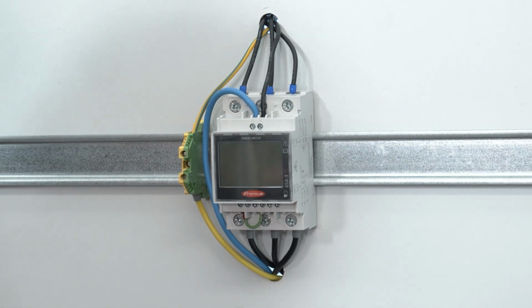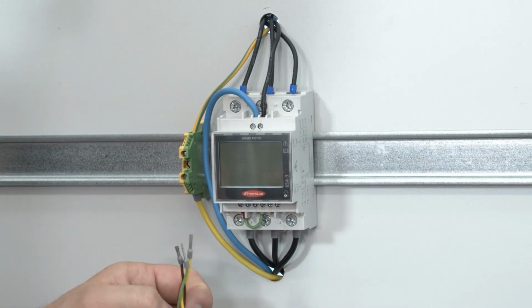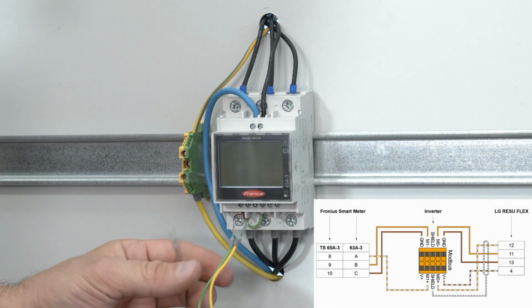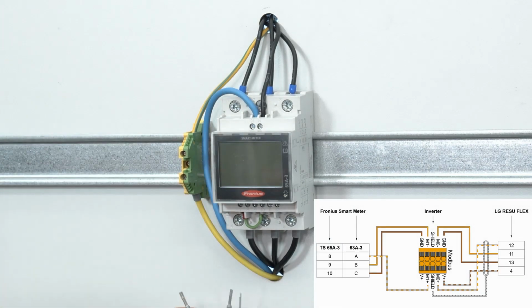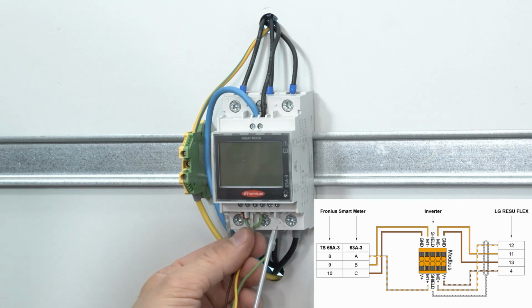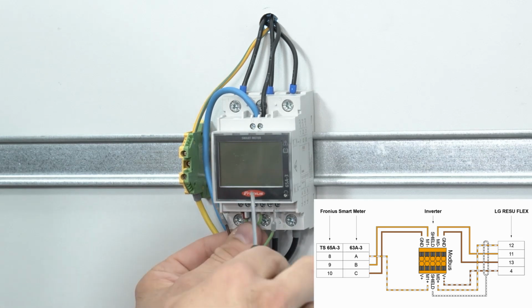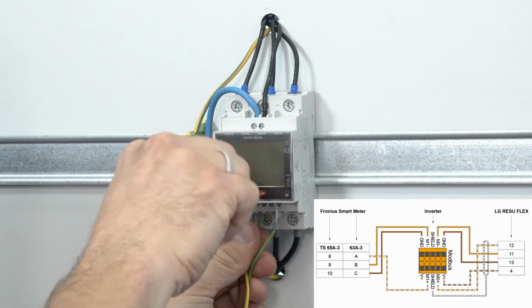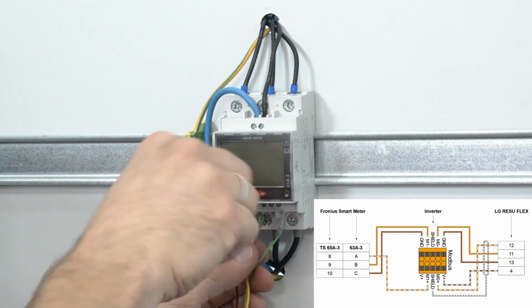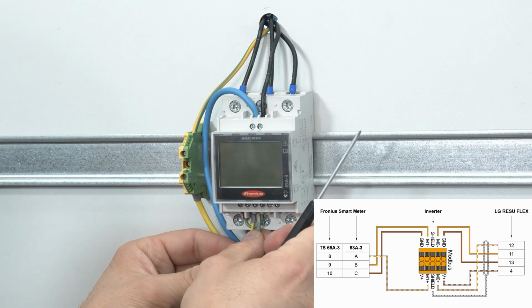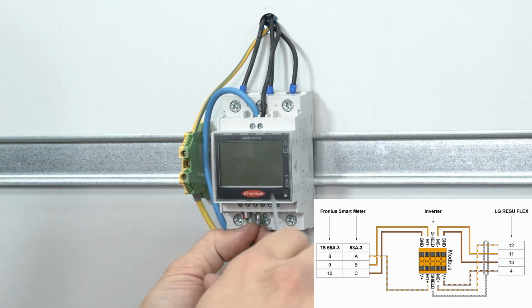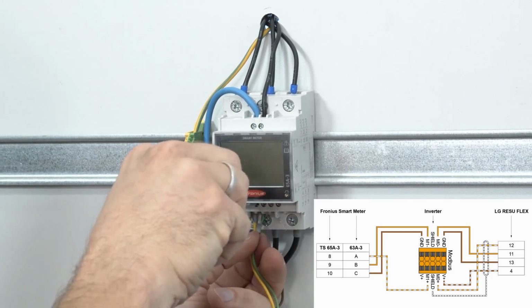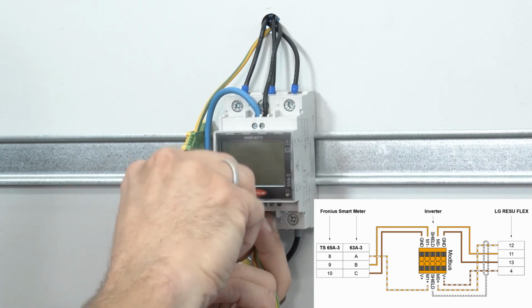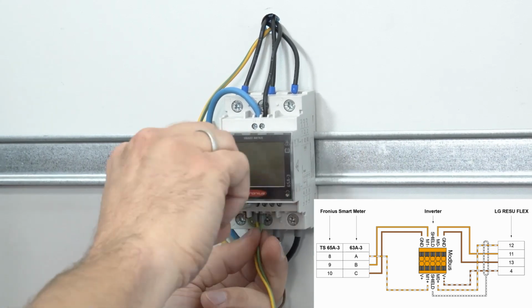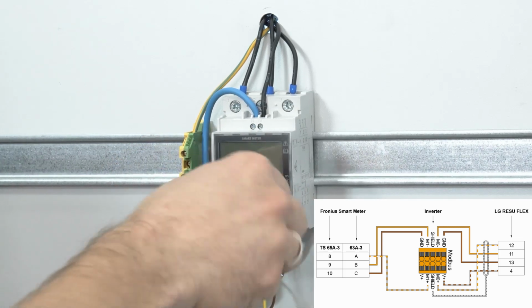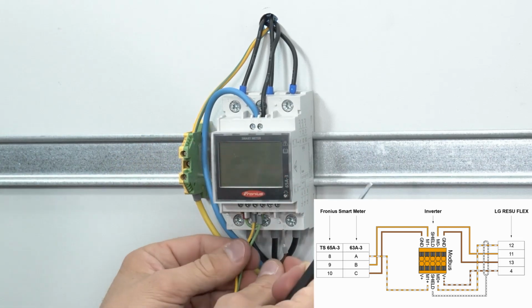contact number 9. And then for the Modbus communication we are again using our data plus, data minus and ground cable, and therefore we are starting with contactor number 8. This is our Modbus Plus, also our M Plus cable. We are installing it to this one. Second up, we are installing to pin number 9 our M minus cable coming from the GEN24 Plus. Together, please note, with the termination resistance, this cable bridge goes into contactor number 9.